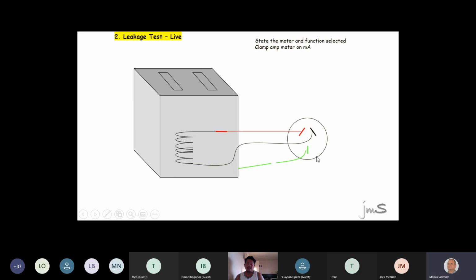Right, so here we go. I'm going to take my special tester. I'm going to put it across the earth. In other words, I'm going to measure current. So you liven it. You switch it on. Don't touch the kettle. You're going to get shocked if there's a fault. And you measure the current in the earth. Guys, a lot of you can't tap into the flex, so you probably will have your own little test lead. Phase, neutral, earth. And you put your clamp meter around the earth.